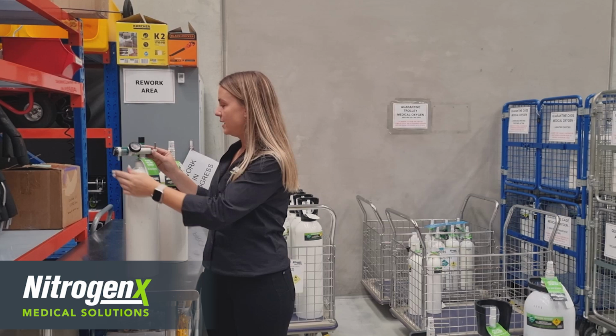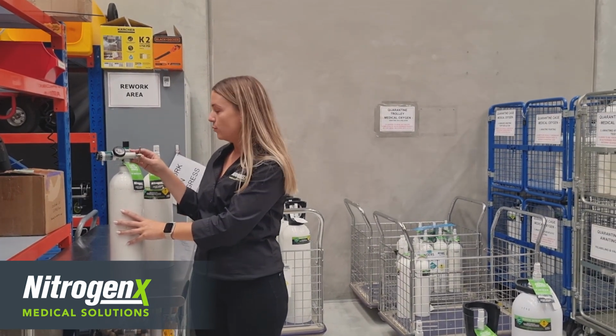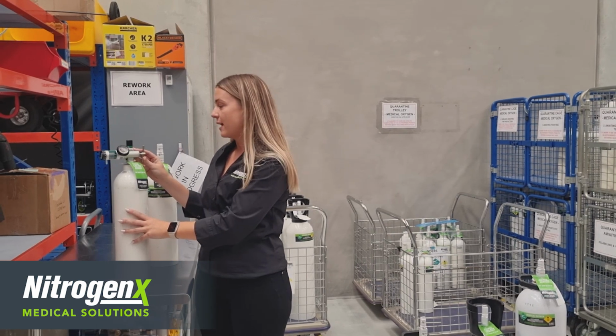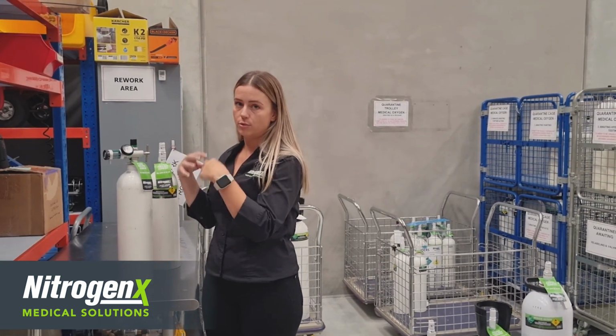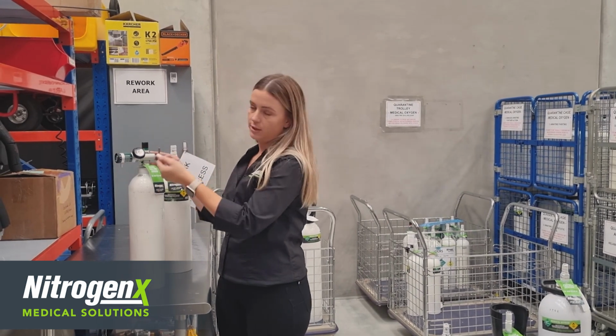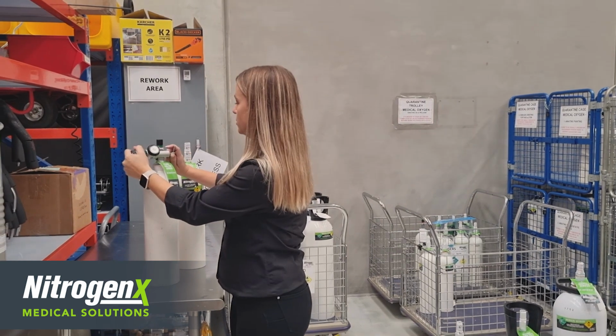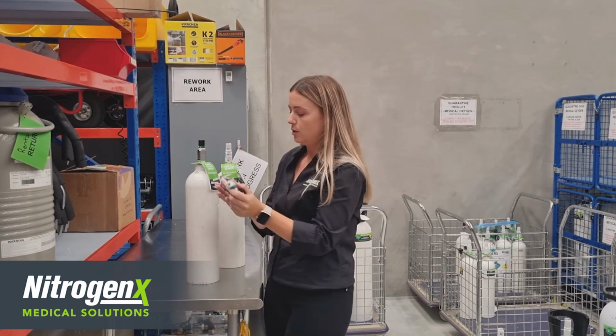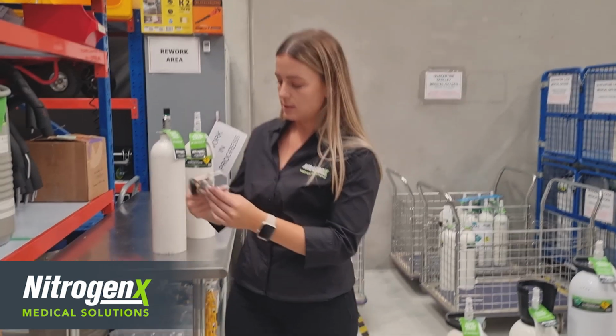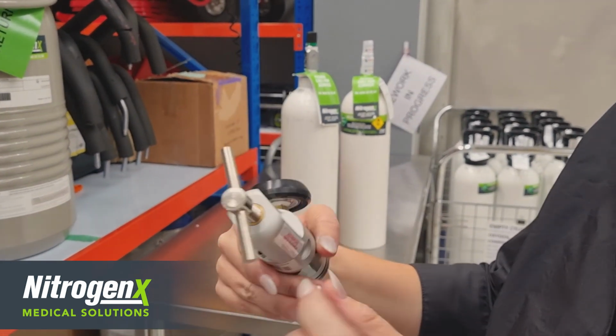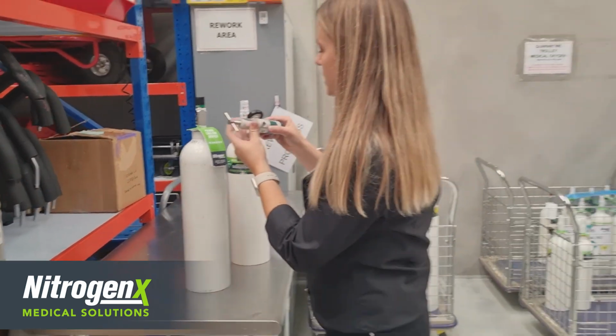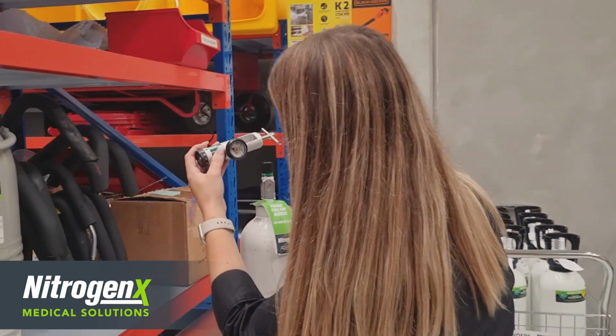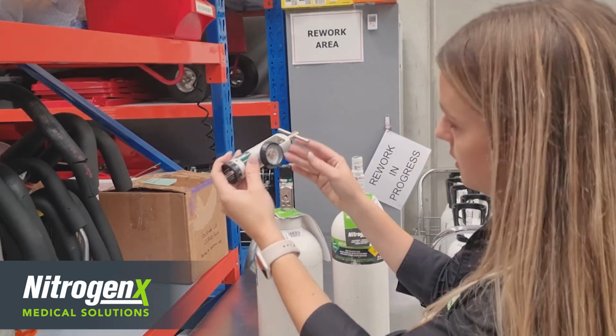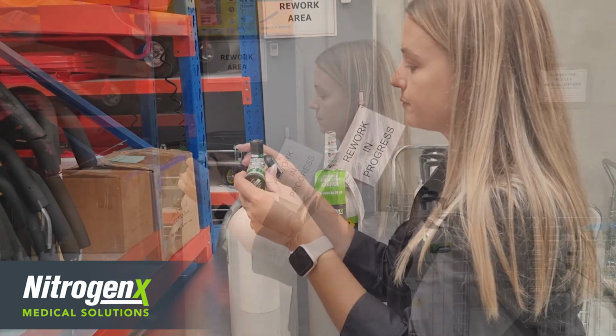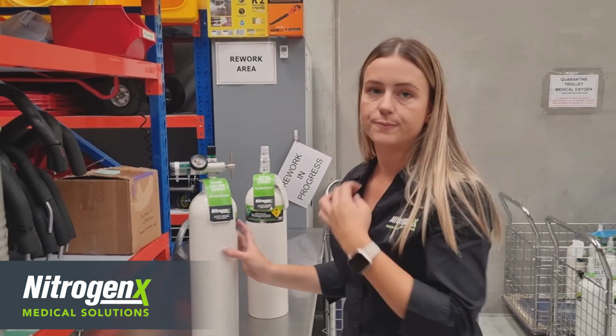Another issue that we commonly see is a regulator not sitting flush. This is usually when the cylinder hasn't been attached correctly. In that case, we would often suggest to the customer that they fully remove the regulator, realign everything, and then reattach it and retest it. So to remove it, we simply untwist it and take it off. We need to double check the indents are going to align on the cylinder and that the metal yoke washer is in there. So to reattach it, you just need to make sure that those are aligning with the holes on the bottle, here and here. Twist it back on, and then just check everything is sitting flush.